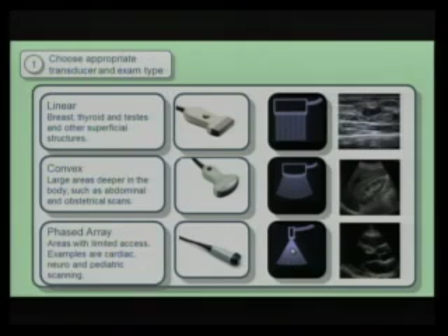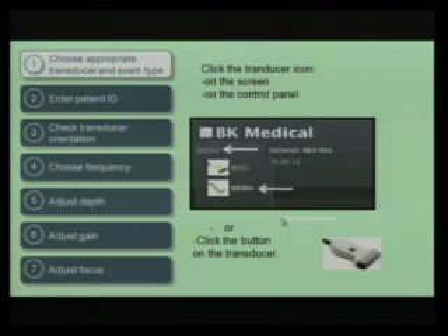This is a linear array transducer that fires sequentially. This is a convex array, which goes a little deeper because it has a lesser frequency, usually for the abdomen, obstetrical. And phased array, which is when you need a little focus to get your transducer, and it can be cardiac, neuro, pediatric scanning. It's good for us for intercostal, okay, and you can see a heart here. So this is B&K, the company that announces these things. So they say here to choose the transducer, you have this way to do it. The one we use, GE, you need to disconnect them, and they're kind of different.